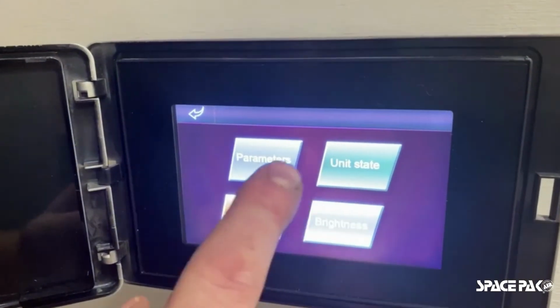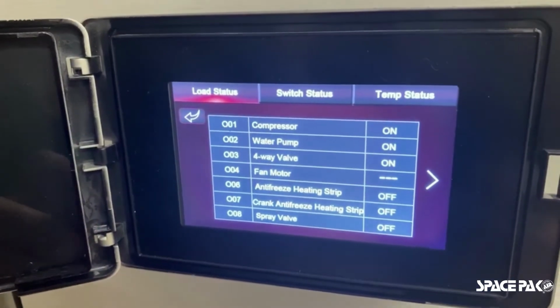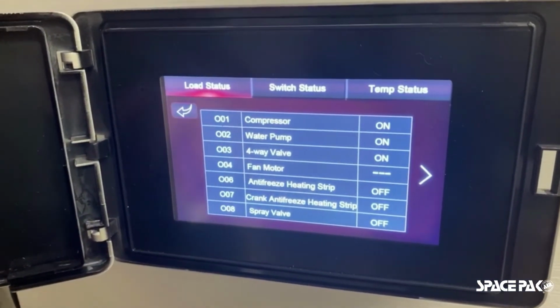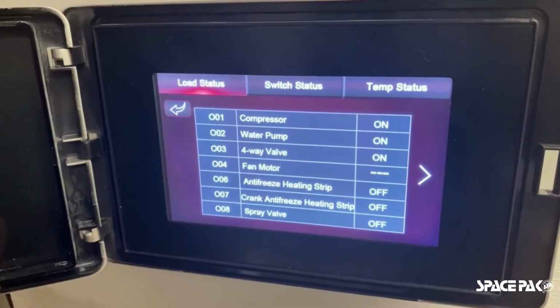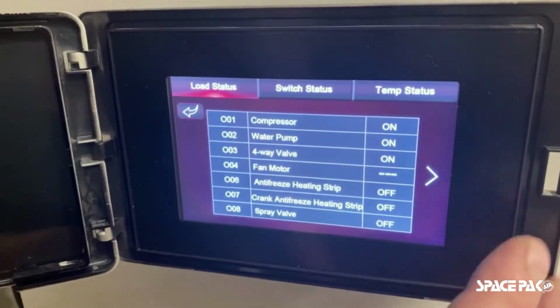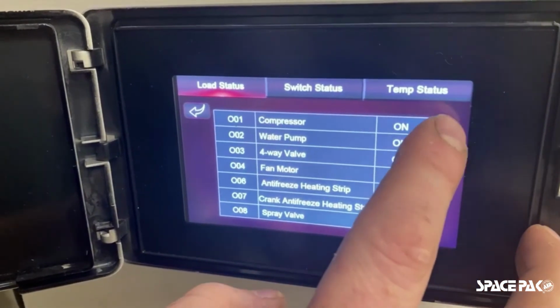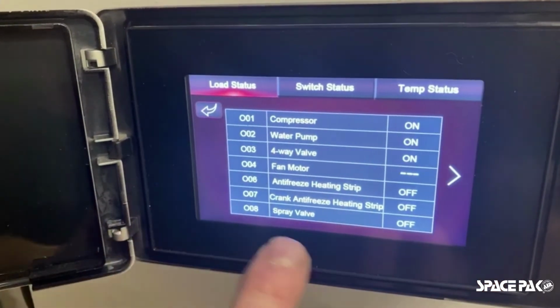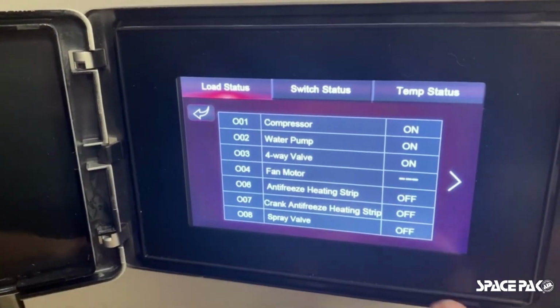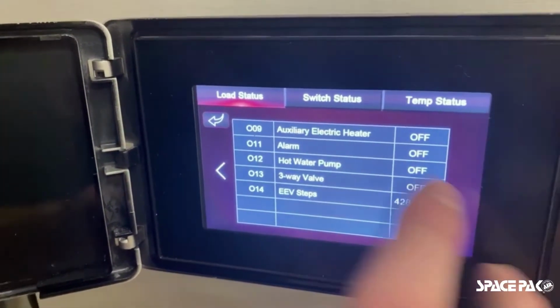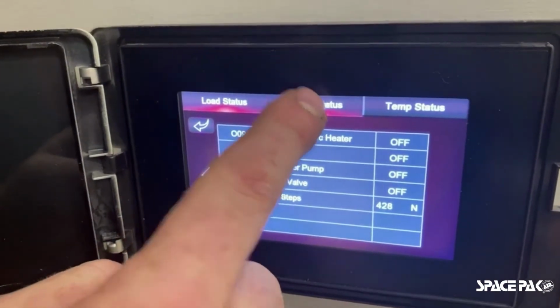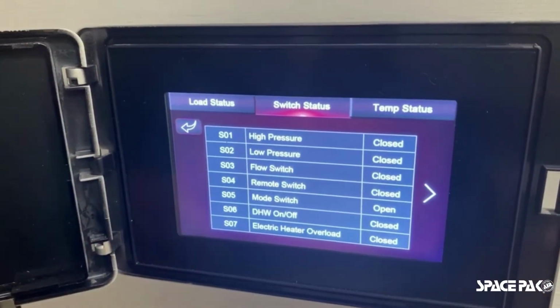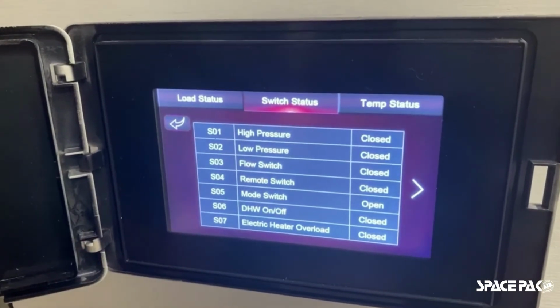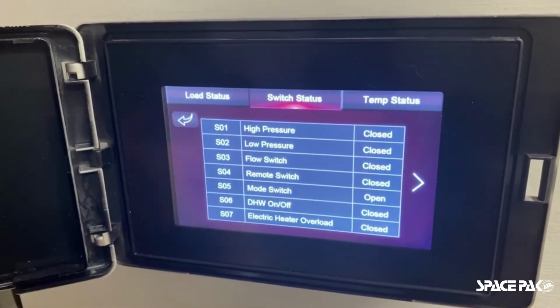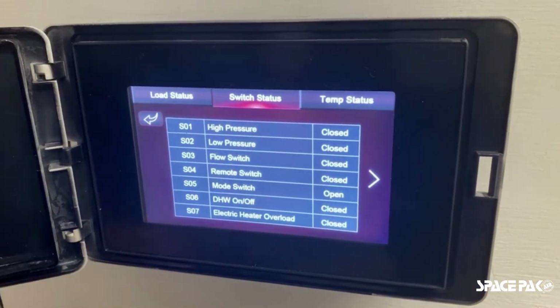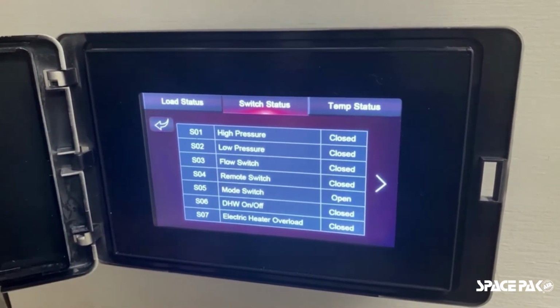Now we can change brightness parameters. We can now go to unit state. Now remember, we're still in number 22, or passcode 22 if you will. This will give us some more information. We've got our circulator pump on, we've got our compressor on, we've got no antifreeze heating strips, we've got no crankcase heaters, auxiliary electric heater, all of that kind of stuff is off. Switch status: high pressure switch is closed. These are refrigerant. High pressure switch is closed, low pressure switch is closed. Our flow switch closed, remote switch closed, mode switch is open, that's why we're in cooling.